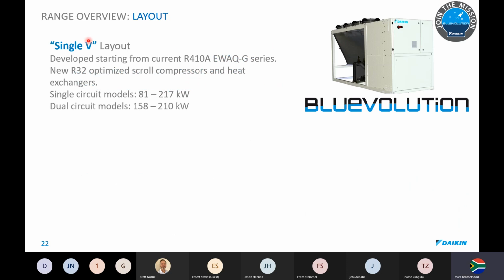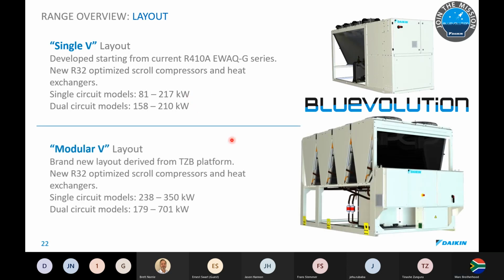Now there are different models. This is what we call the single V block. The condenser is in the shape of a V. It was developed starting from the current R410 range that we have phased out, and we've put new R32 refrigerant in, and we've optimized the compressors as well as the heat exchangers. So we go single circuits as well as offering dual circuits. Then we also offer what we call a modular V. So we've pretty much taken this V block and turned it sideways. And we offer this as well in single circuits up to 350 kilowatts and in dual up to 701 kilowatts.